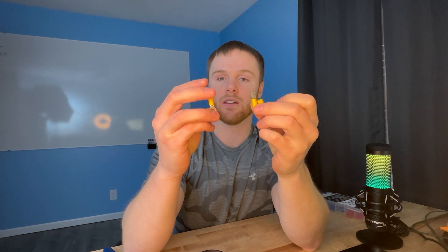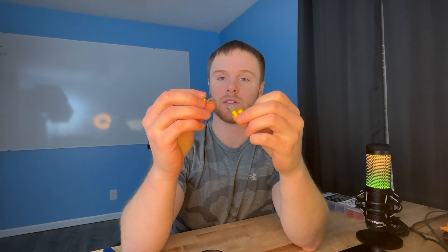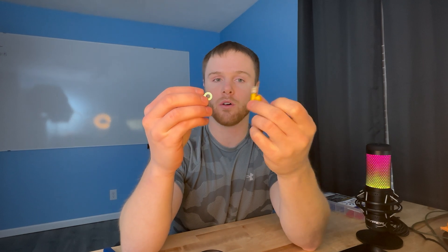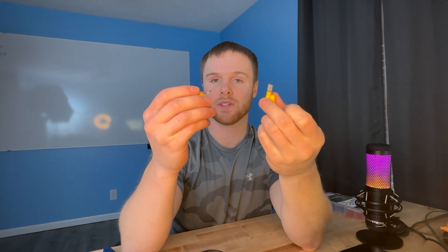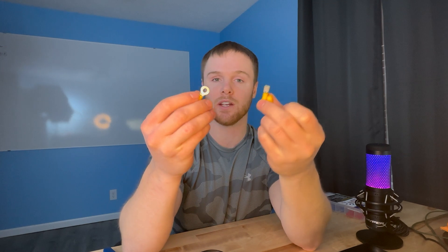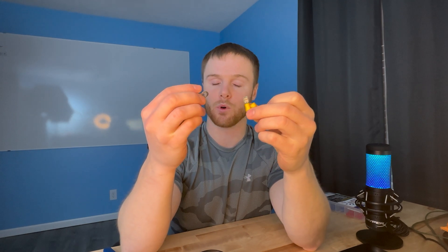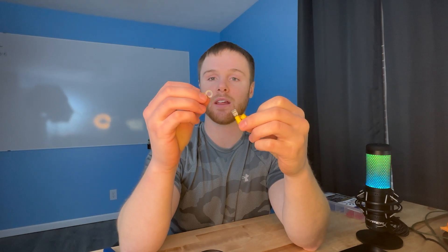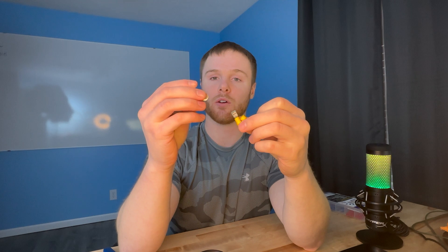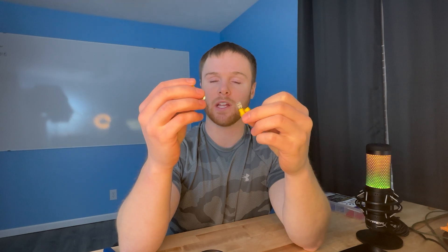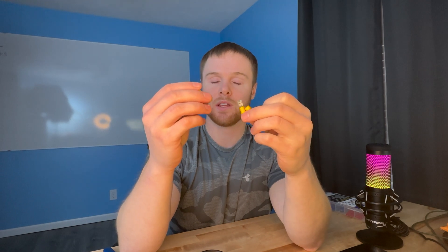Speaking of proper rating, all of these are rated accordingly. All these yellow ones that I have here are either 10 to 12 gauge, rated for 10 gauge wiring, and they're okay up to 30 amps. That's why I double checked. Some are, some aren't, and sometimes they do use different coloring.